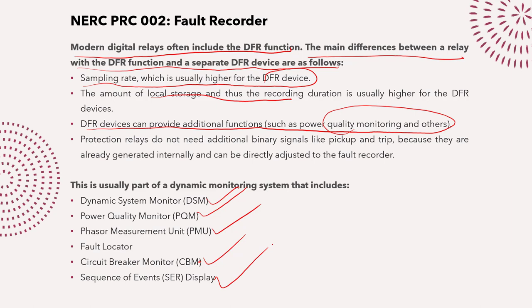Standalone DFR devices can sample at very high rates and store different data sets by performing back-end calculations. Depending on the recording capabilities and input provided, they can act as a PMU, dynamic system monitor, fault locator, circuit breaker monitor, or sequence event recorder. These different data sets are generated by performing back-end algorithmic calculations on the high-rate sampled data.